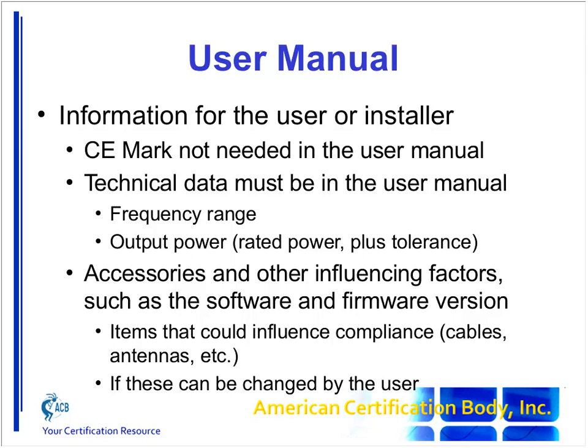If the user could change the software, and if that software could affect compliance or performance, that needs to be listed in the user manual. You need to make it clear to the user which software versions they're allowed to use and which accessories they're allowed to use.